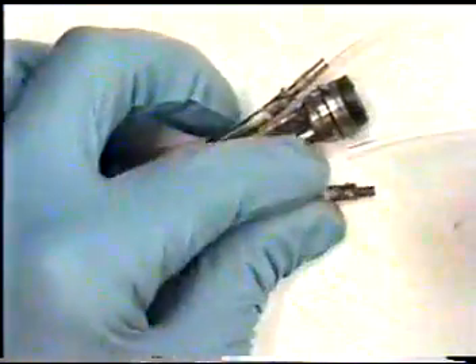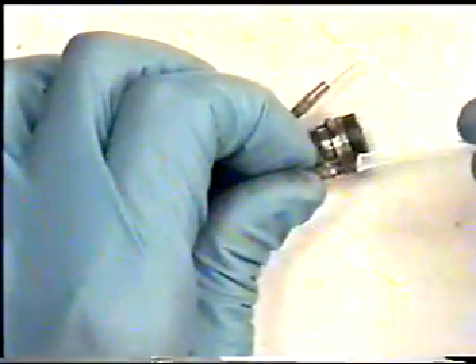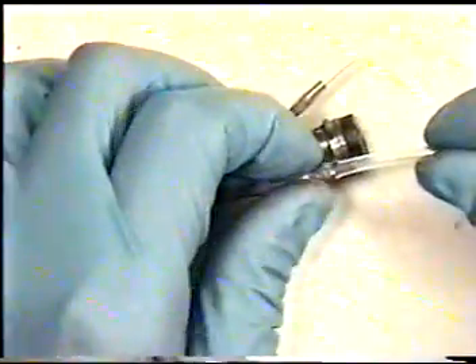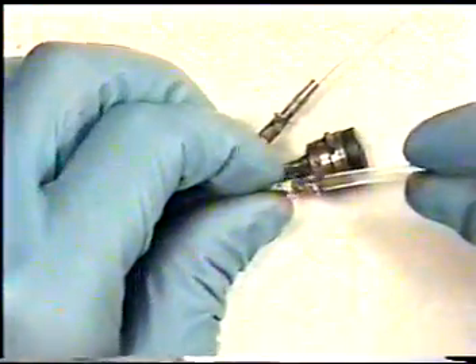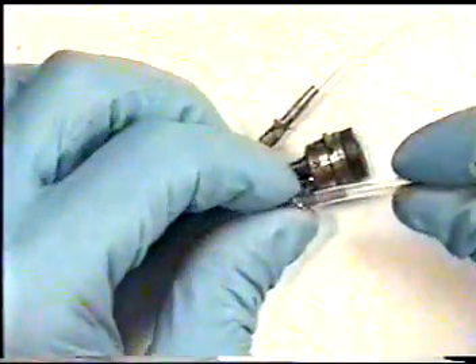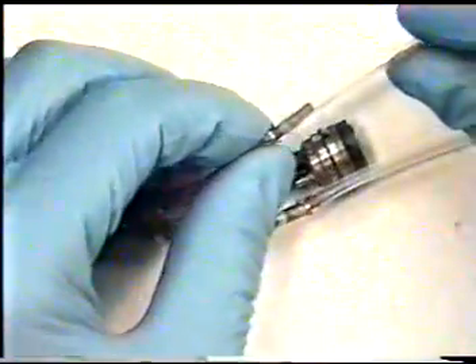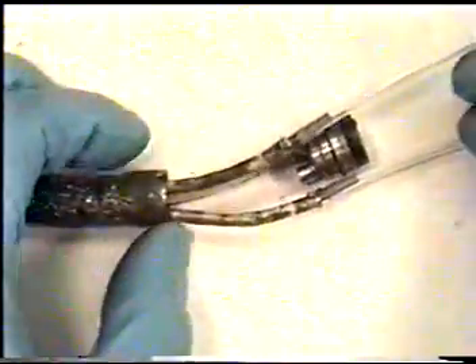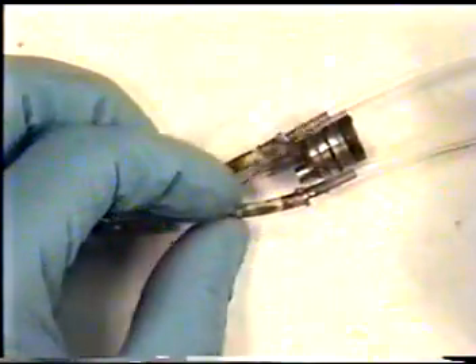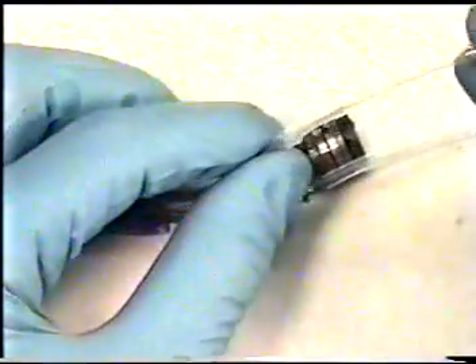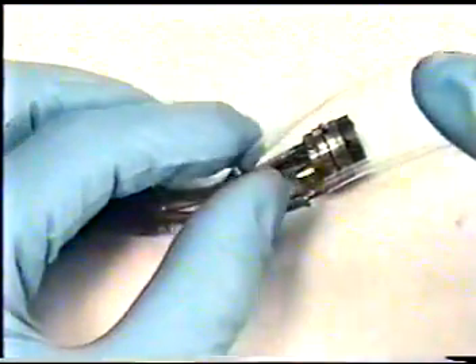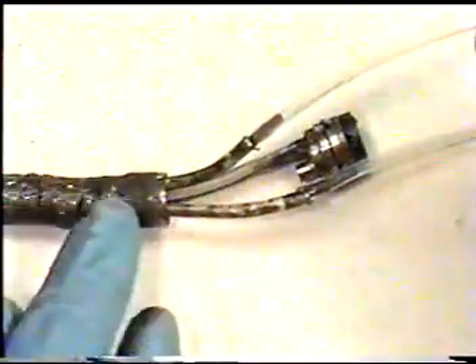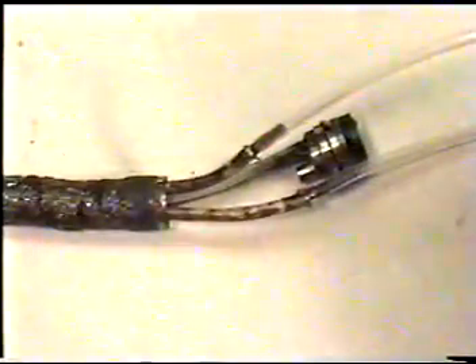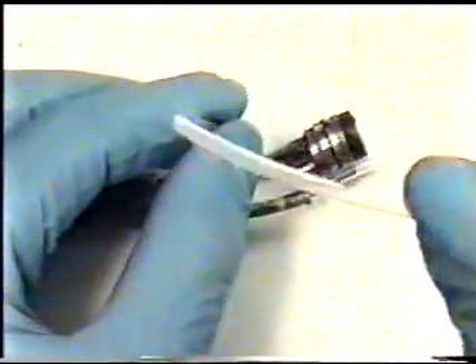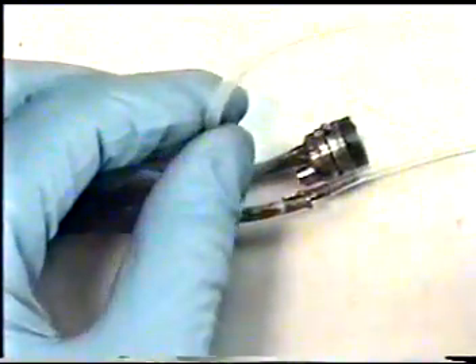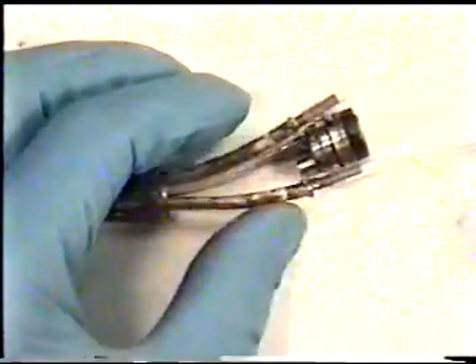Connect the tubing to both of the light guide illumination bundles. Be sure they are somewhat tight fitted onto the ends of the light guides so we can pull both of these through. Use a piece of tubing which is of course longer than your insertion tube so we can pull it completely through. It will need to be double the length of the insertion tube, our plastic tubing.